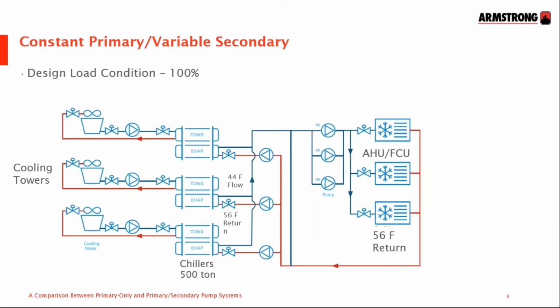So let's put some numbers to our design and operate the system at varying loads and see how the chillers and pumps are sequenced in and out. At design, 100%, we have three pumps, each at 1000 GPM, dedicated, pumping through the three 500-ton chillers, which cool the water from 56 degrees coming back from the building down to 44 degrees going back into the building.